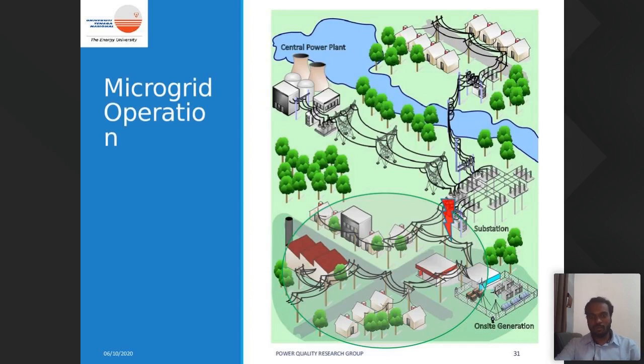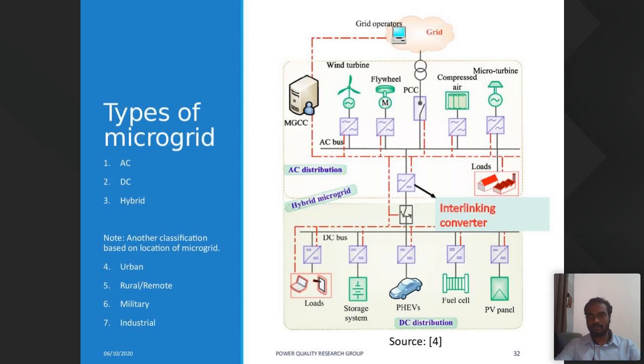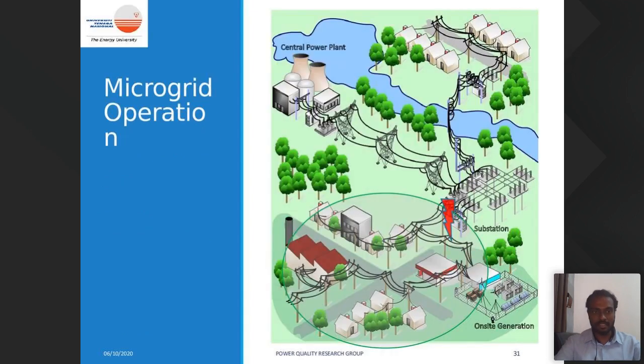So we will see the operation of a microgrid, where we have on-site generation in the marked area and a fault occurs at the substation level, at the distribution substation. Sorry, I think the animation is not working here, so I'll just explain. Once the fault occurs, the microgrid controller isolates the marked area to its islanded mode and continues to power its load using the on-site generation. So with a microgrid, you can have high resiliency of operation to the load.